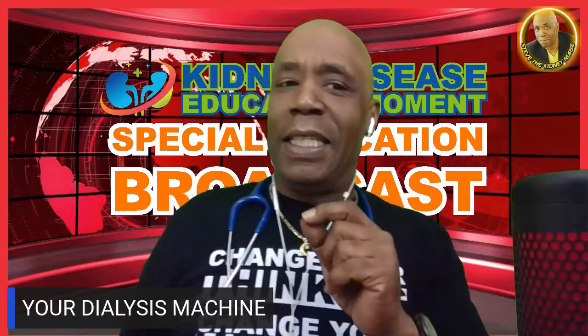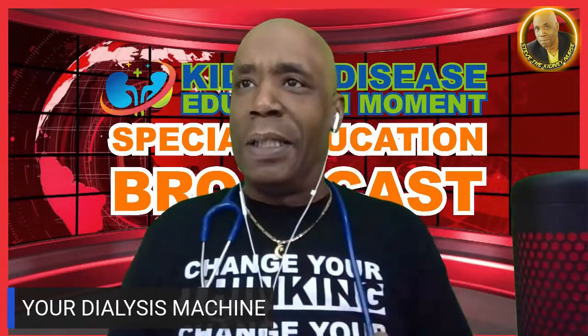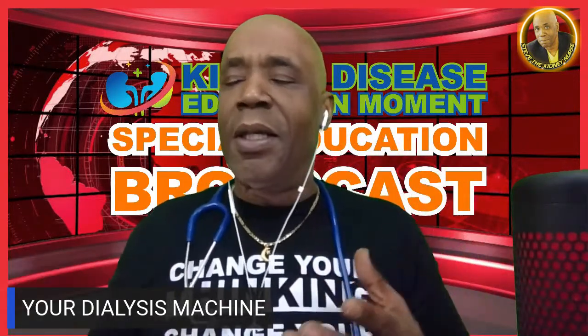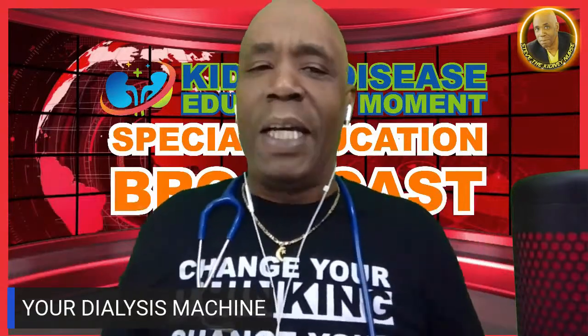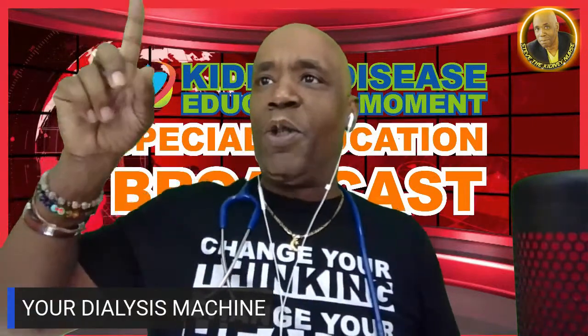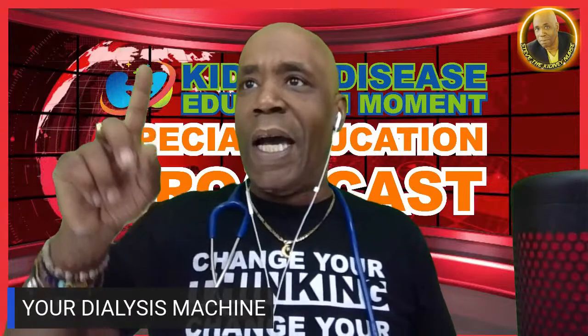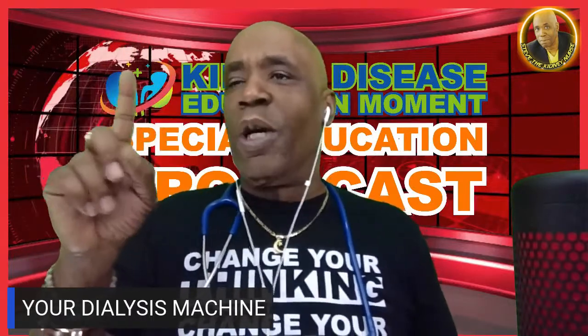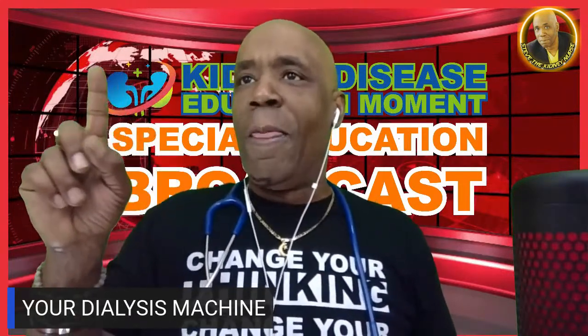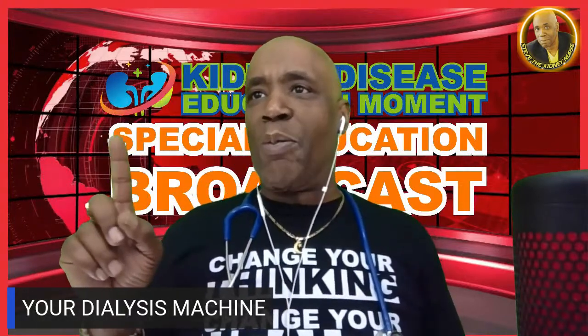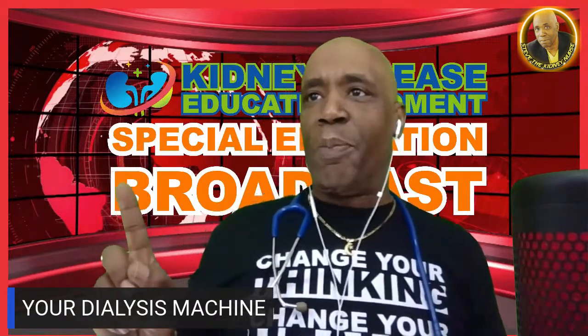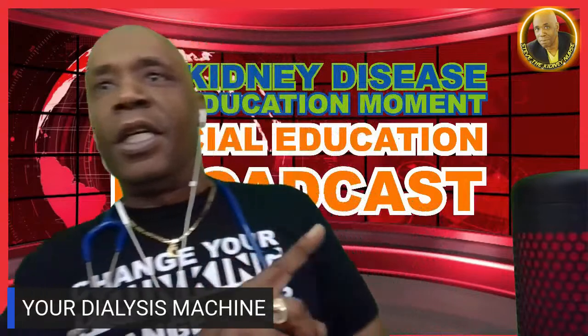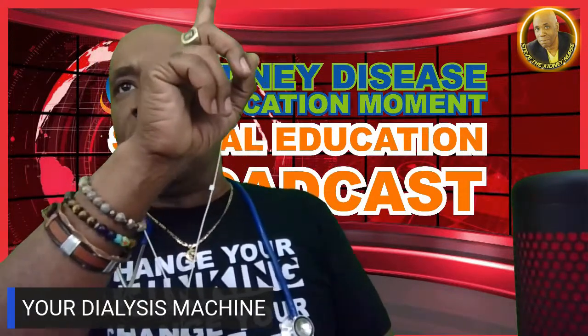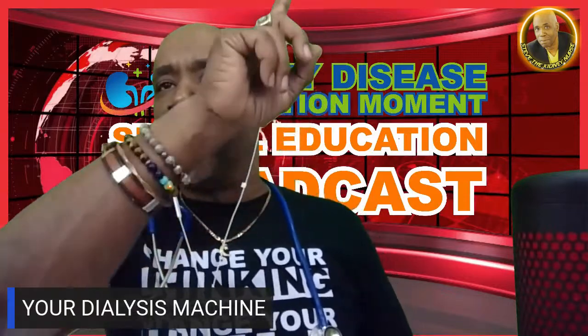So the technicians and the nurses, they program your treatment, whatever your orders are. Or let's say, for instance, you're supposed to take off 3 liters. They're going to put 3 liters up there, your treatment time, right? And then once they program that in, the rate is going to come out, meaning how much fluid is taken off or removed per hour. And this is how much has been removed, right? And then you got your profiles down here and your other switches that go into the machine. This starts the treatment where it says treatment pause. You got your TMP, transmembrane pressure, your venous pressure, which monitors the venous needle, and the arterial pressure.